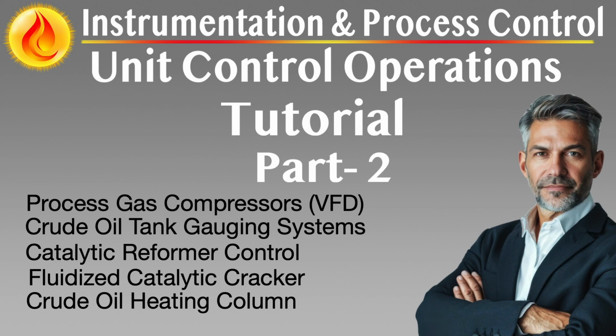Instrumentation plays a central role in enabling fine-tuned column control. Guided wave radar, GWR, or differential pressure transmitters are used for accurate bottom-level monitoring, while pressure-compensated thermocouples ensure reliable temperature data even under two-phase flow conditions. Inline composition analyzers or naphtha cut point estimators can feed inferential quality control loops that adjust flash conditions based on product blending requirements or downstream unit constraints.